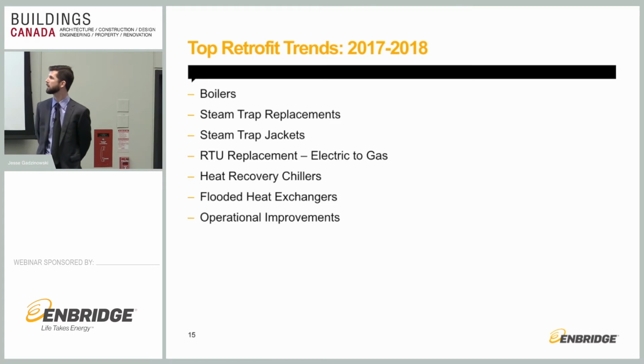Flooded heat exchangers, like I said, subcooling that condensate, using more of that heat, it's a good opportunity. And then operational improvements. We have a Run It Right program, which I will talk about later, but a lot of buildings now, they've done a lot of the large retrofits, especially the A-class, everyone's got everything done, all the new systems are there, things look great, but how do we make sure the building's gonna operate consistently and well over time? So that's what we're seeing, people coming to us for operational improvements.